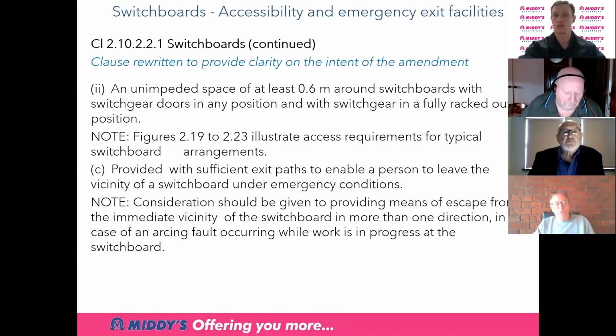We've had a lot of issues in regards to the size of doorways into switchboard rooms. Openings or doorways to the switchboard room shall have an unobstructed height of not less than 2 metres and an unobstructed width of not less than 900. That's been reduced in line with the NCC. We've still got the recommendation that you do have the door heights at 2.2 metres, because switchboards can be built to 2.1 metres high. So if the builder doesn't provide a doorway of that size, you may not get your switchboard in. We do have an exemption there, though. The requirement need not apply when replacing the existing switchboard in the same location with a switchboard of the same or lesser rating, just like a repair. That's really what it comes down to.